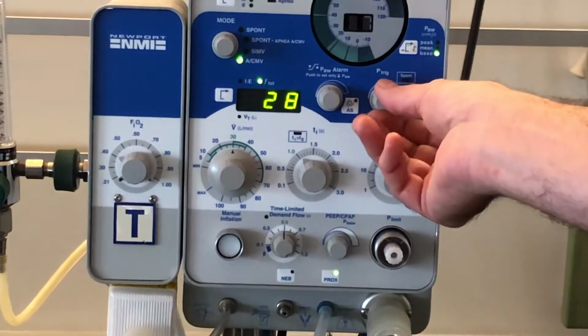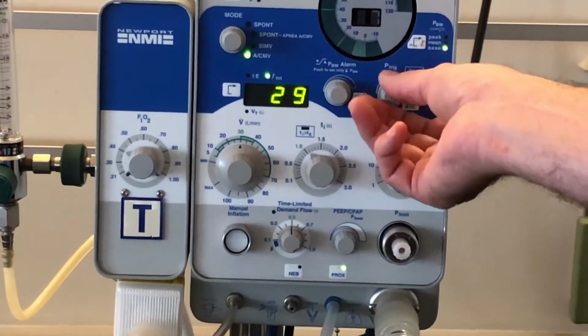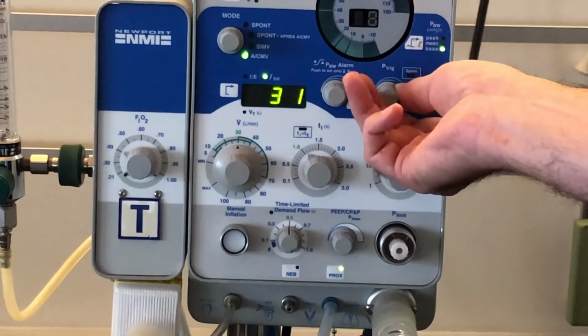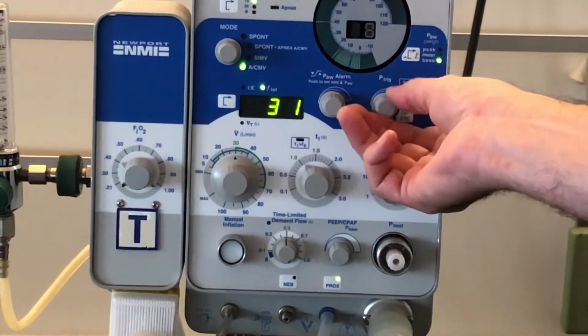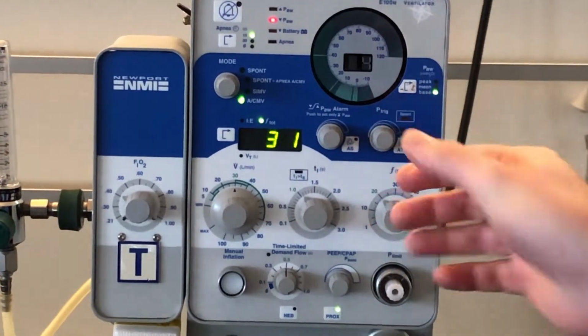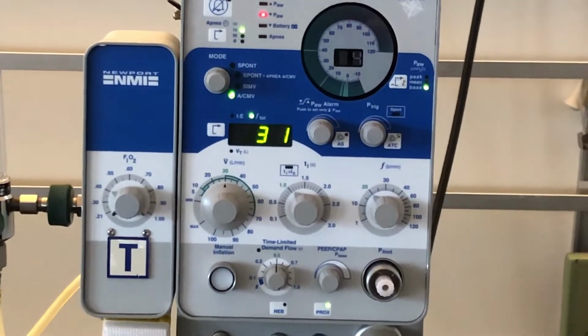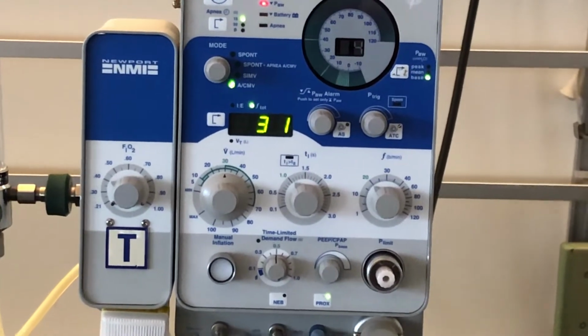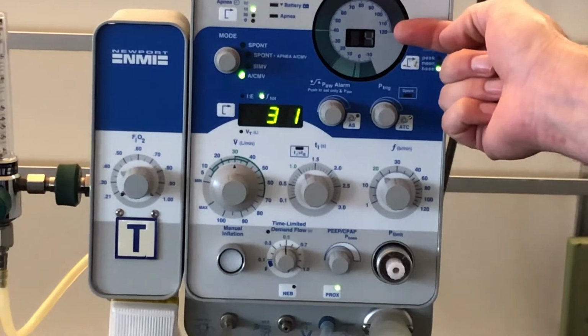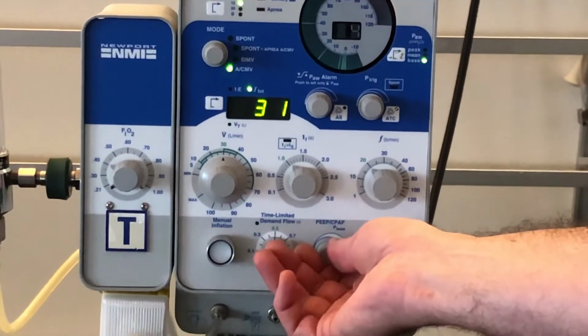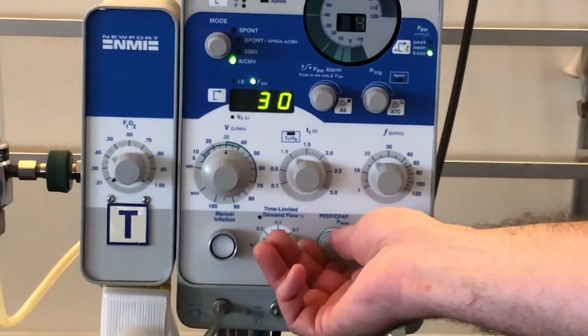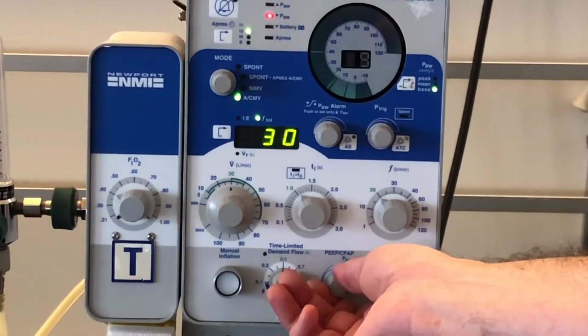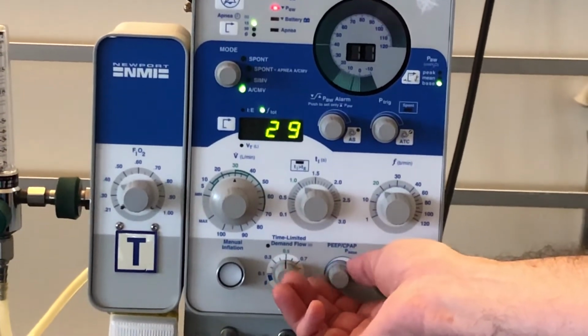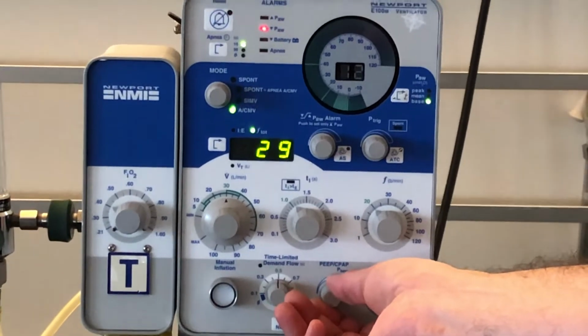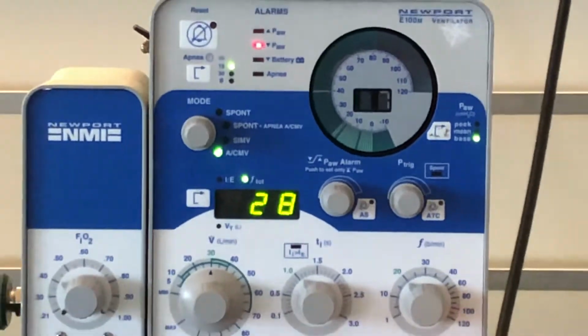Okay, I'm just going to take the trigger and set the trigger higher. Sorry, set the trigger lower. Okay, there you see the auto-triggering has stopped. You'll see because there's no auto-triggering, the baseline pressure has changed. So I need to go and adjust the PEEP setting on the machine now. And I said we'd go for about 8. There we go. I'm getting there.